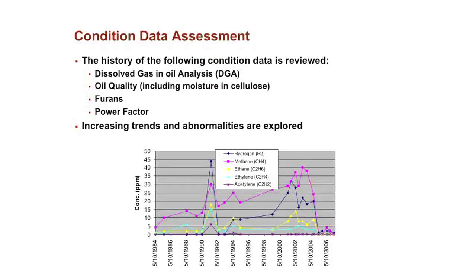Okay. So other things, you look at the condition of the DGA, and we talked about that a lot, and that impacts a lot. It impacts the dielectric, the short circuit, and the thermal risk factor differently. The oil quality of a transformer is very important. So this is the acidity in the oil, which tells you what type of sludging has built up over the years in the oil. The interfacial tension is important. The dielectric strength of the oil is important. Furans, as I was saying before, can give you a good measurement of the age of the cellulose, and then the power factor of the oil. So all these things are important in calculating the condition for all the different aspects of the risk factors.